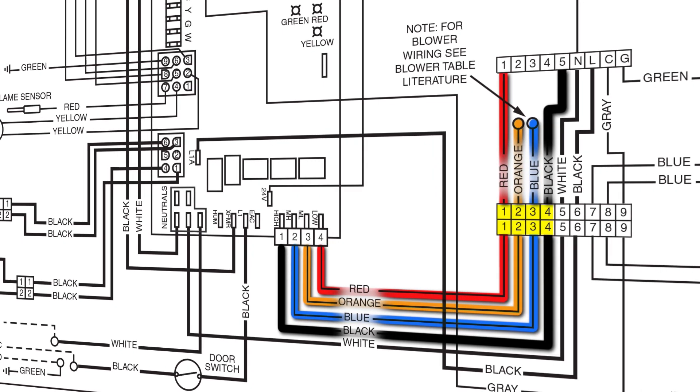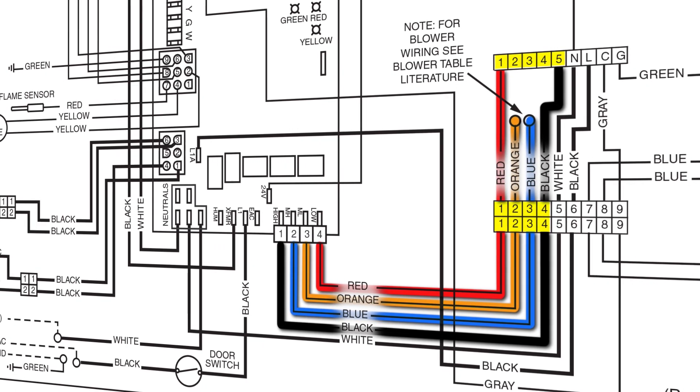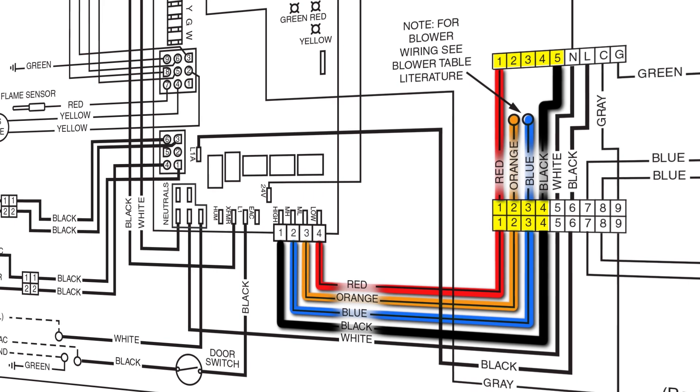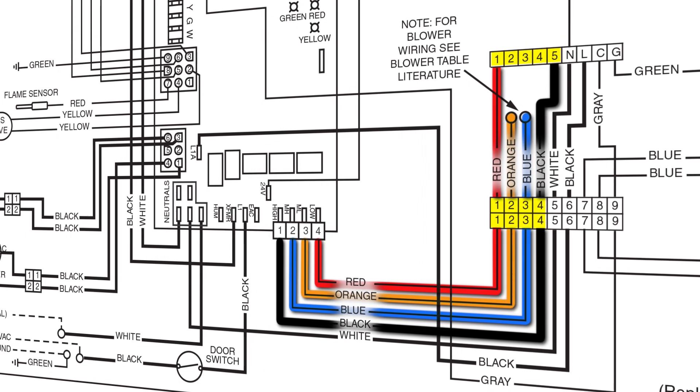So depending on what speed you want to select, you can switch up one of those color wires and put it on one of the speeds that's not selected on that nine pin plug, and that will give you a fifth speed option.